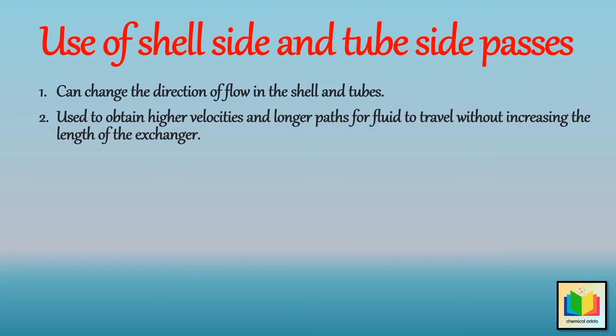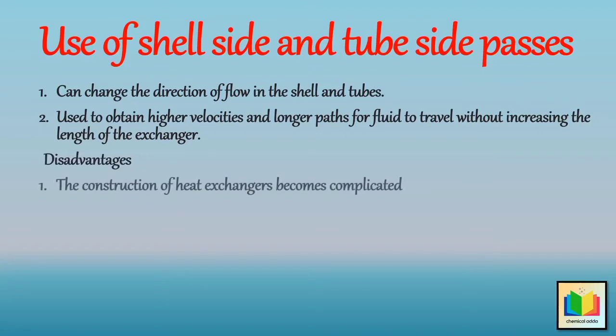Hence, the multi-pass construction decreases the cross section of the fluid path, which increases the fluid velocity, due to which the heat transfer coefficients also increase. However, these have certain disadvantages — due to partition, the construction of heat exchangers becomes complicated and also creates high friction losses.